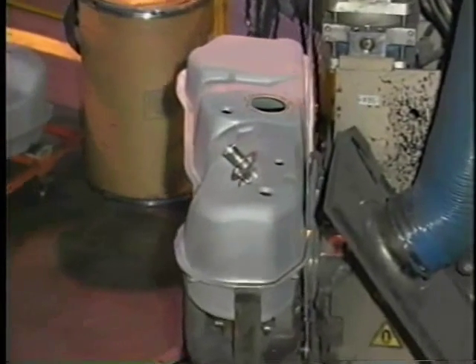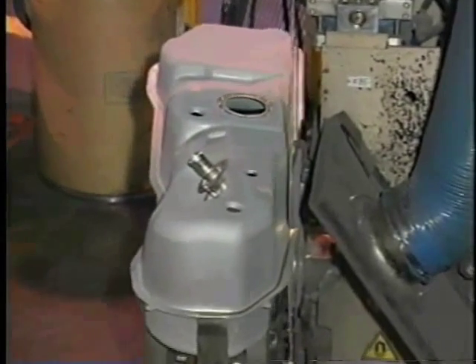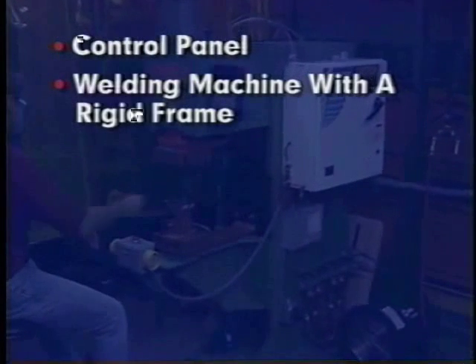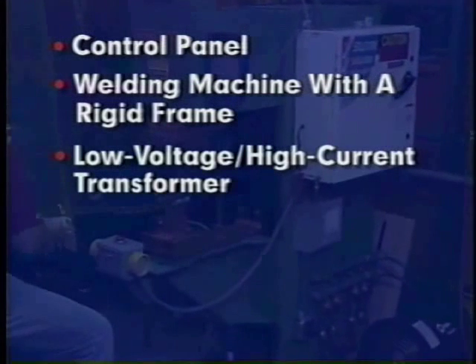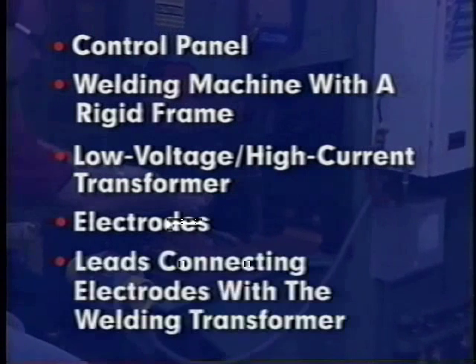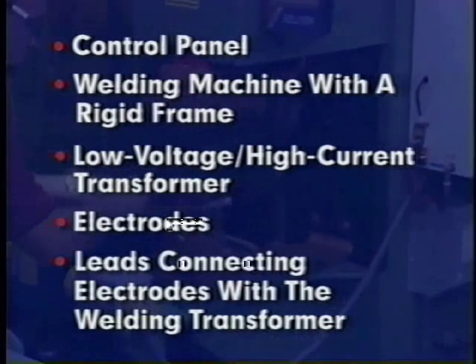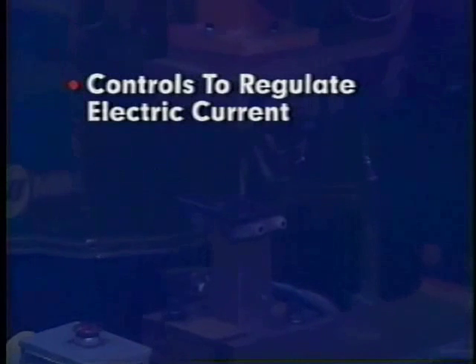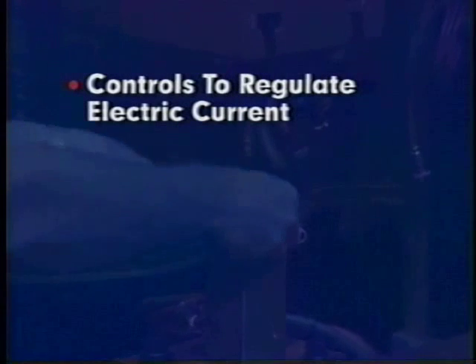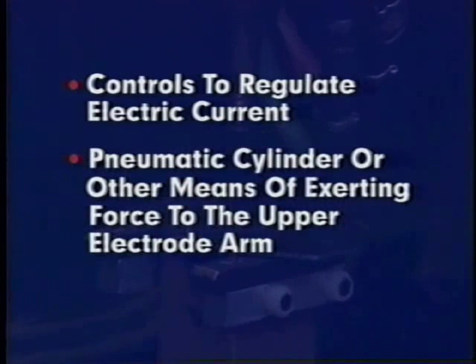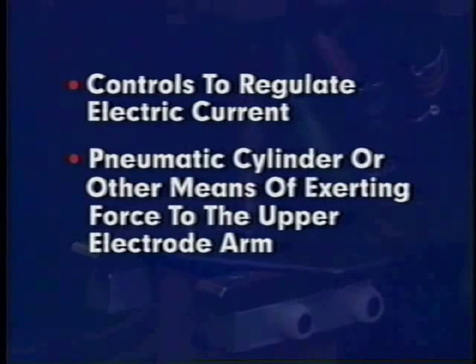The typical resistance welding system consists of a control panel, a welding machine with a rigid frame, a low voltage high current welding transformer, electrodes, leads connecting the electrodes with the welding transformer, controls to regulate electric current, and a pneumatic cylinder or other means of exerting force to the upper electrode arm.